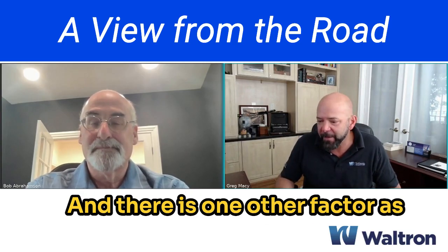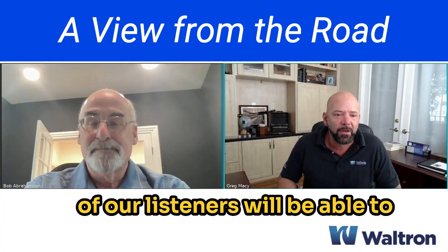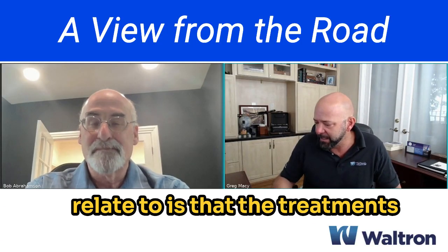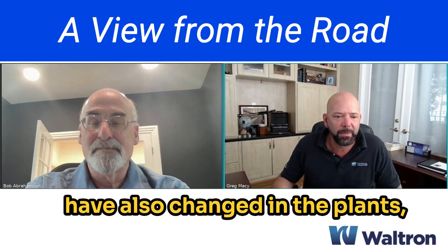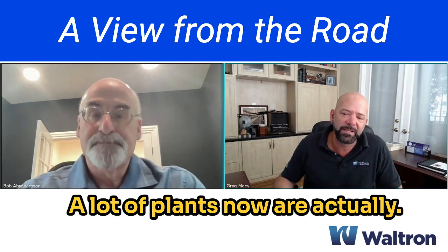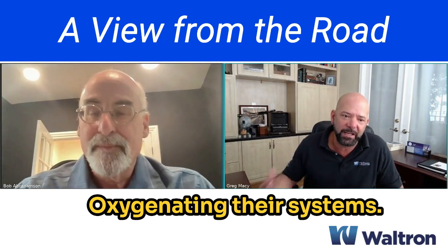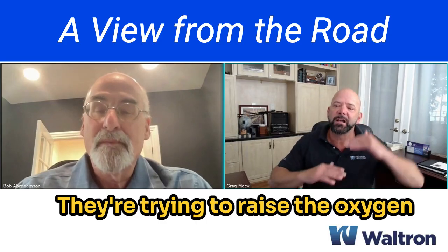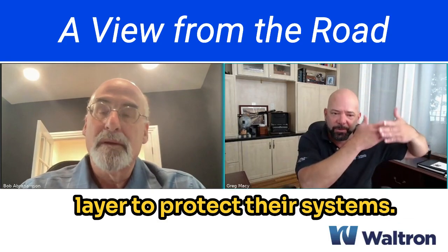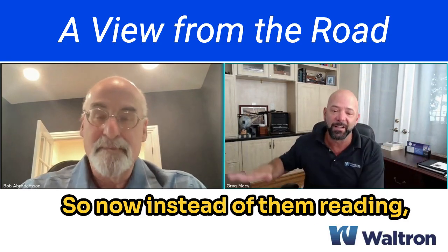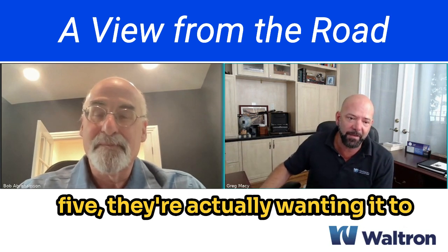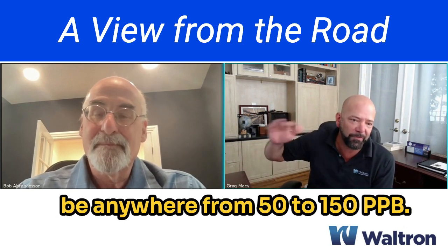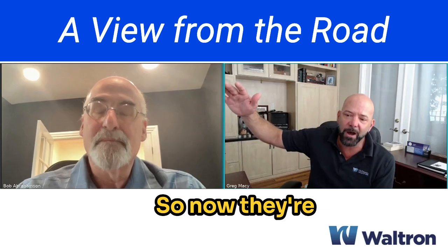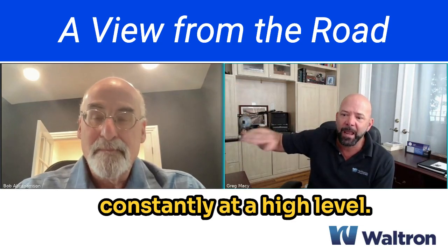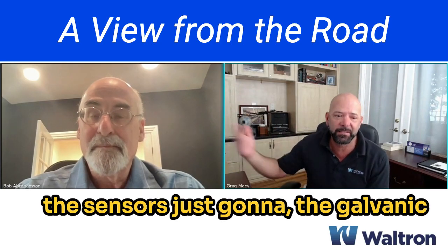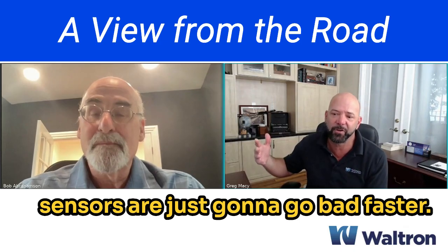That's really what we're seeing in the field now that these plants are cycling more. There's also another factor listeners can relate to: treatments in plants have changed. A lot of plants now are actually oxygenating their systems, trying to raise the oxygen up to create a rust layer to protect the system. So instead of wanting DO less than 5, they're wanting it anywhere from 50 to 150 ppb - constantly at a high level. In those applications, the galvanic sensors are just going to go bad faster.